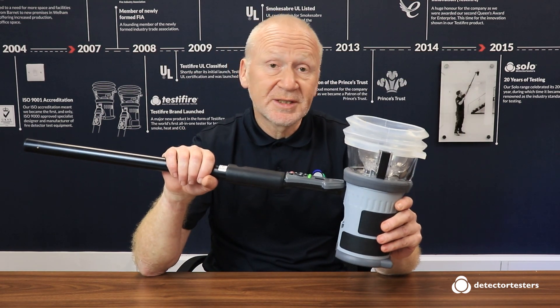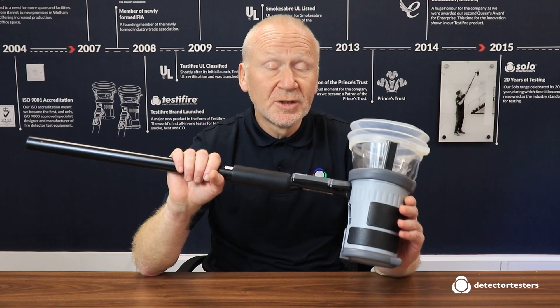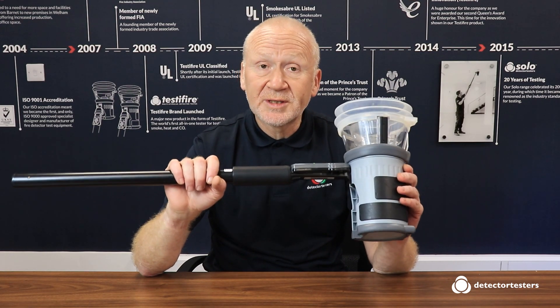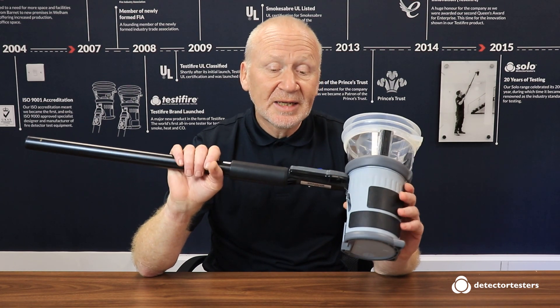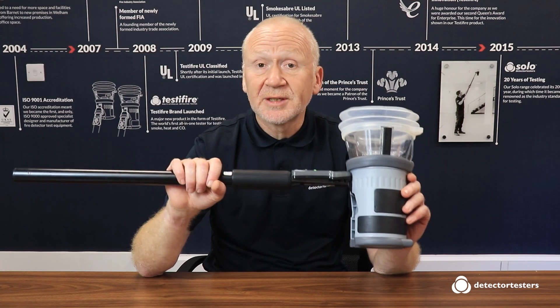The Testifire 2000 has the ability to produce smoke, heat, and carbon monoxide. It uses capsules, so it has all the advantages we covered previously. Plus, it's an all-in-one tester, so the engineer just has to carry one test tool with them, which means they always have the right tool to hand. It will also test multi-sensors as well as single sensor detectors.